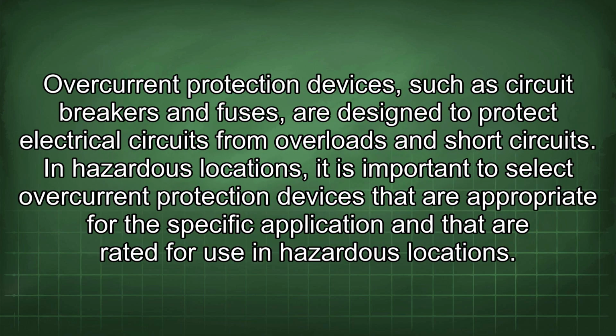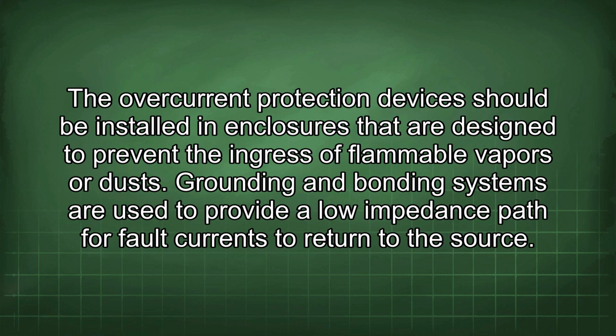Overcurrent protection devices, such as circuit breakers and fuses, are designed to protect electrical circuits from overloads and short circuits. In hazardous locations, it is important to select overcurrent protection devices that are appropriate for the specific application and that are rated for use in hazardous locations. The overcurrent protection devices should be installed in enclosures that are designed to prevent the ingress of flammable vapors or dusts.